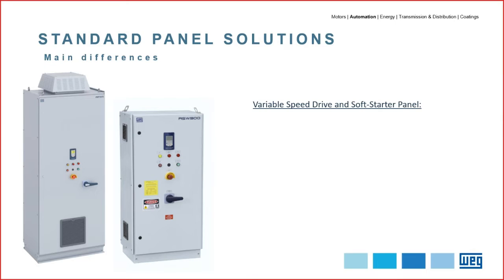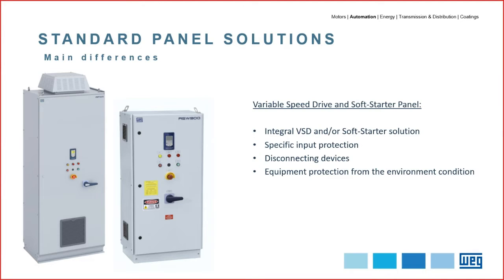On the other hand, a panel must be considered when the requirements are a little bit more complex and complete. For example, when the application demands a specific input protection circuit and disconnecting devices. Also, when it's necessary to protect the VSD or the soft starter from the environment condition where it is installed, like from moisture, corrosion, dust, and any other aggressive conditions.